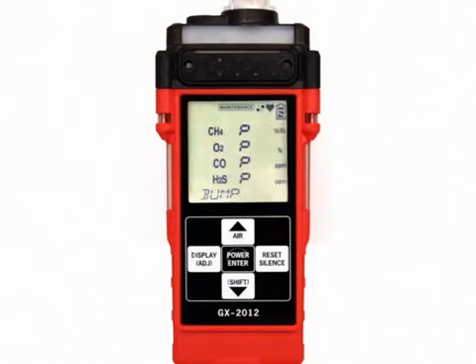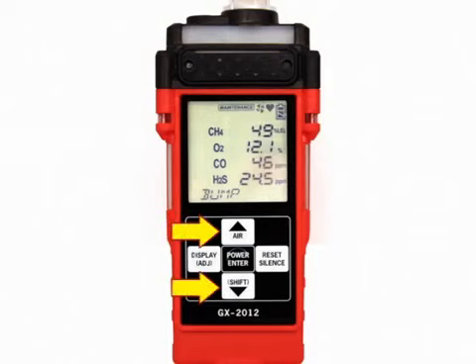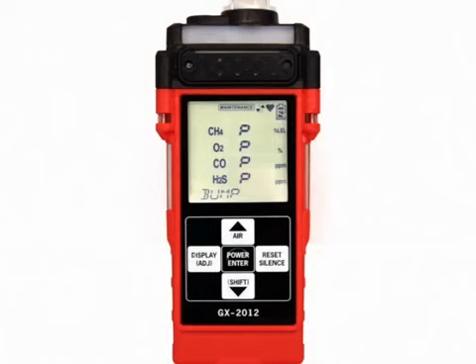When AutoCal in the Bump Set menu item in maintenance mode is set to on and all channels pass the bump test, the following screen appears. To view the bump test gas readings, press the Air or Shift button. You can scroll between the bump test results and the bump test gas readings with the Air or Shift buttons. To return to the bump screen in calibration mode, press power enter.